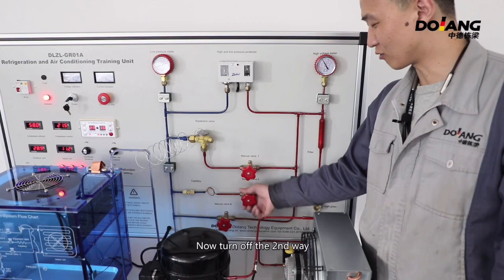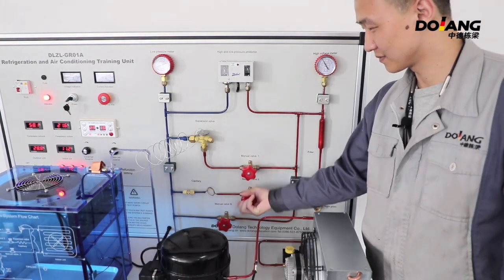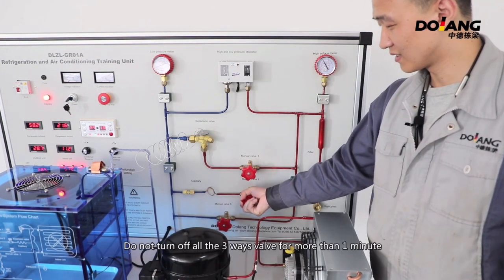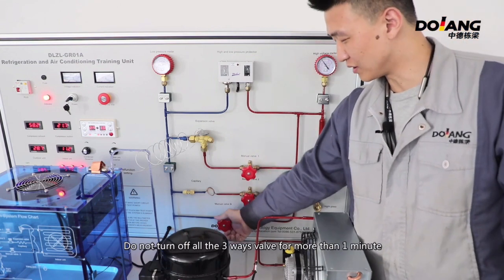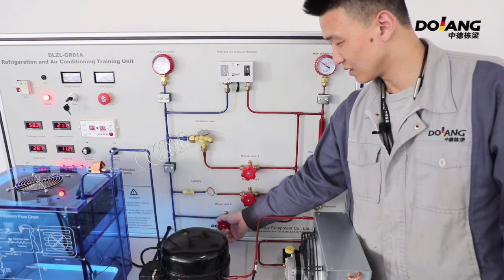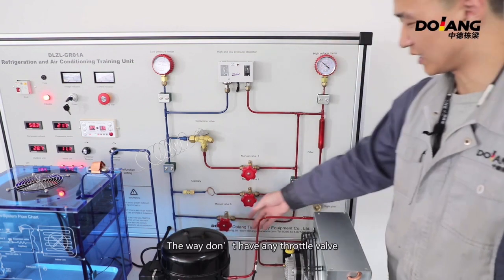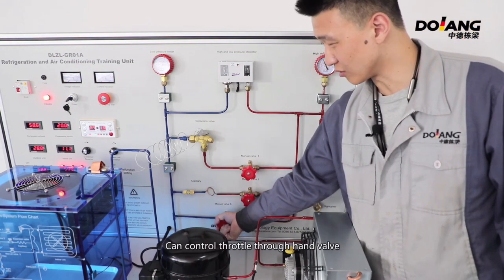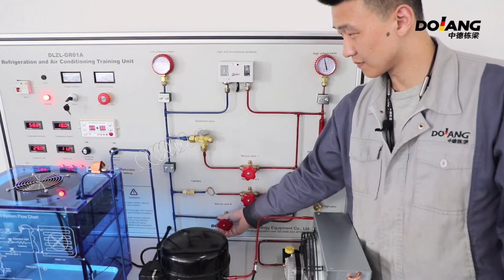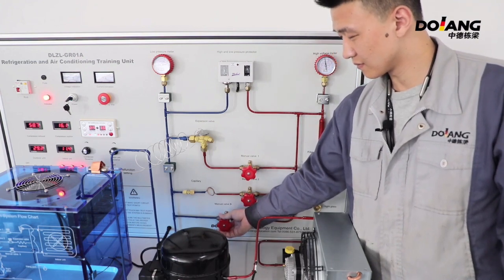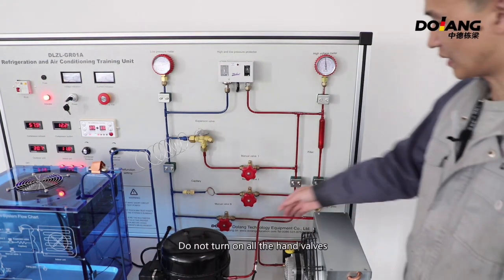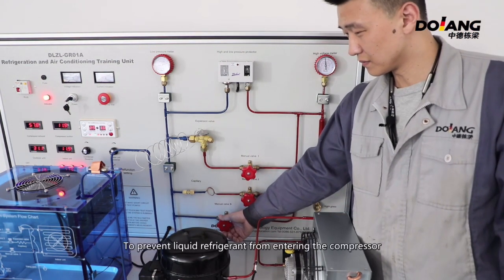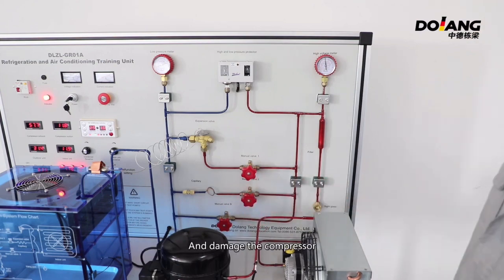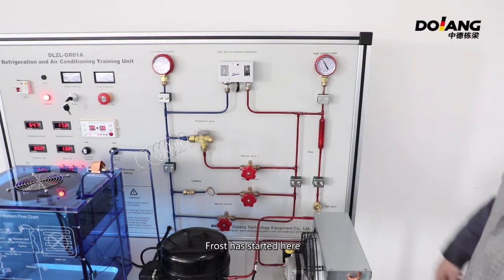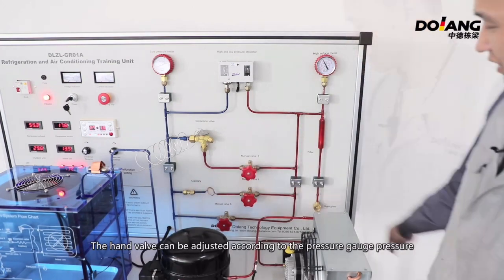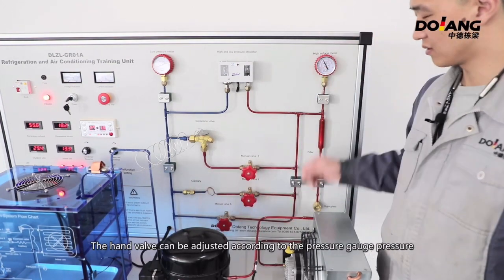Now turn off the second way. Do not turn off all the 3 ways valve for more than 1 minute. The way doesn't have any throttle valve. Can control throttle through the hand valve. Do not turn on all the hand valves, to prevent liquid refrigerant from entering the compressor. Frost has started here. The hand valve can be adjusted according to the pressure gauge pressure.